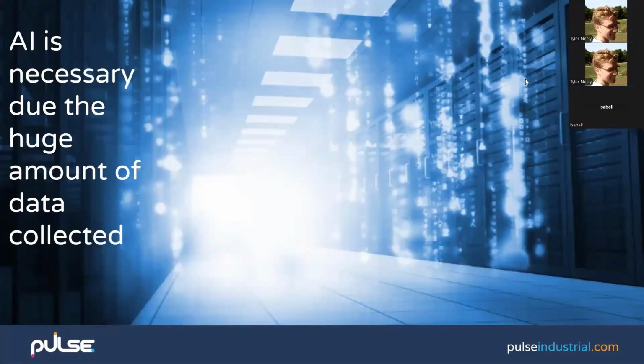Some facility steam systems are more active within certain parts of the day or run on time cycles. Example, we have a brewery customer that has kettles that run 2 hours on and 2 hours off. The artificial intelligence system learns its baseline behavior and is able to trigger an alert outside of that as well when there is a change in data on the trap. The artificial intelligence is able to look at other traps in the facility as well. So it looks at traps that are in a neighboring capacity and identifies that there could be a potential change to the entire system, like a steam site shutdown.